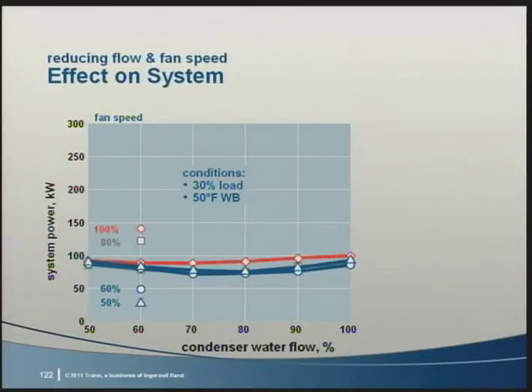Our final example examines the same system at 30% load and a wet bulb of 50 degrees. The system power consumption is fairly flat. One thing to note is that reducing the tower fan speed makes sense at all water flow rates. This reiterates what we saw earlier when we covered cooling tower control. Just because chillers can operate with colder entering condenser water temperatures does not mean it's optimal.